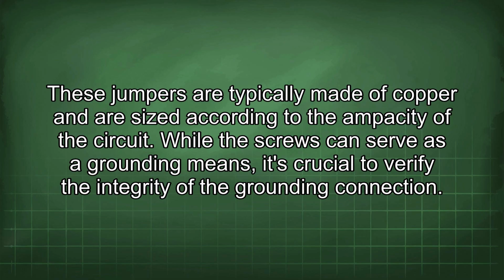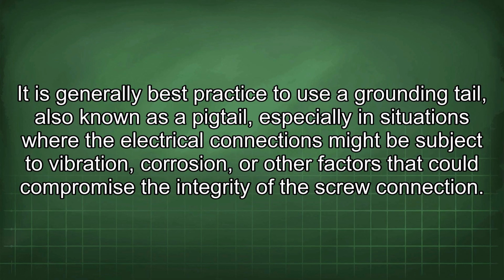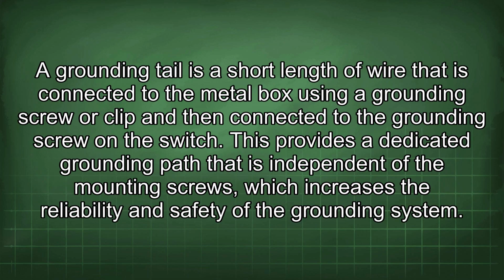While the screws can serve as a grounding means, it's crucial to verify the integrity of the grounding connection. It is generally best practice to use a grounding tail, also known as a pigtail, especially in situations where the electrical connections might be subject to vibration, corrosion, or other factors that could compromise the integrity of the screw connection. A grounding tail is a short length of wire that is connected to the metal box using a grounding screw or clip and then connected to the grounding screw on the switch. This provides a dedicated grounding path that is independent of the mounting screws, which increases the reliability and safety of the grounding system.